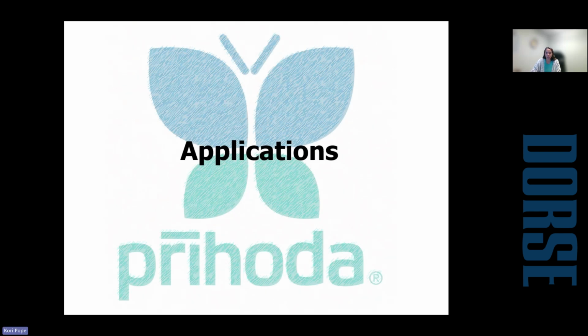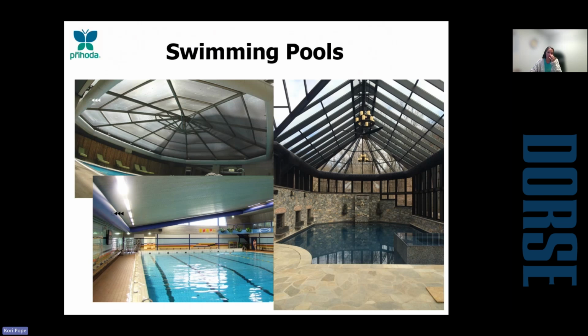I have just a few more slides here to show you guys, and this is just going to go over the different applications for fabric duct. So everybody knows swimming pools. It's one of the most common applications, mainly because of the benefits for the fabric duct diffusers here. You don't have to worry about any type of rust or corrosion. You also don't have to worry about condensation because these typically are a little bit more of a humid environment.